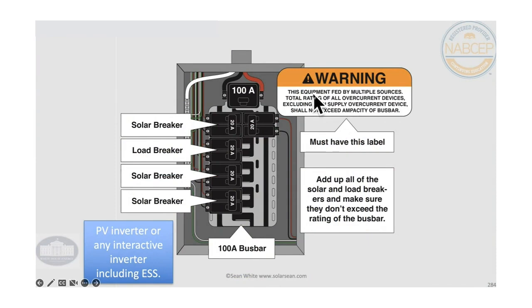I call it the sum rule. You ignore the main breaker. If the main breaker wasn't there, it wouldn't make a difference because you are protecting things in reverse. To make things less confusing, we do add the load breakers onto this calculation, and we don't do it based on 125% of inverter current. So just all the breakers can't exceed the rating of the bus bar. That's all there is to it right there. And so I like to call it the sum rule, or the sum of the breakers rule.